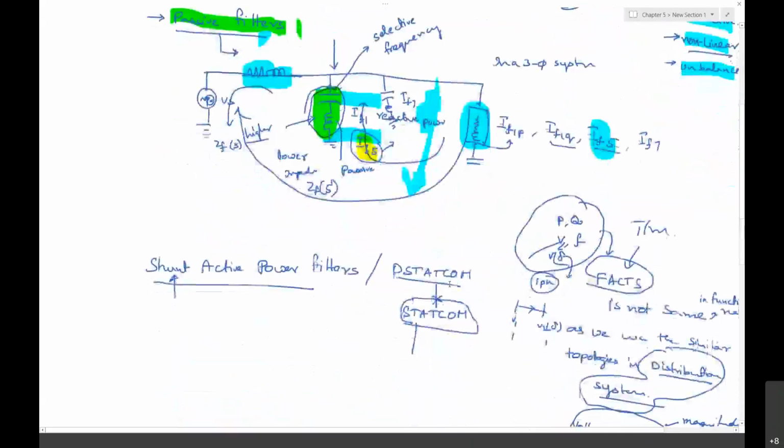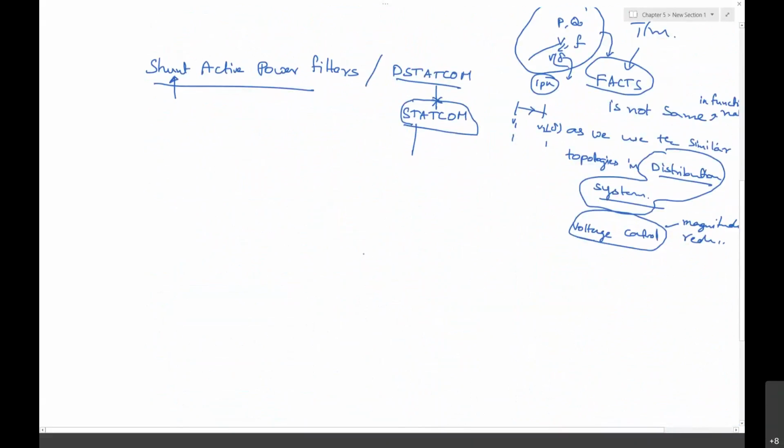Based upon the requirement of the load, if the load requires the fifth and maybe the seventh, then we need to design a filter for each. Initially this is designed for the fifth, and then this for the seventh harmonic. Maybe over time the connected load no longer produces the fifth harmonic current, and then keeping that filter in the line is not required at all.